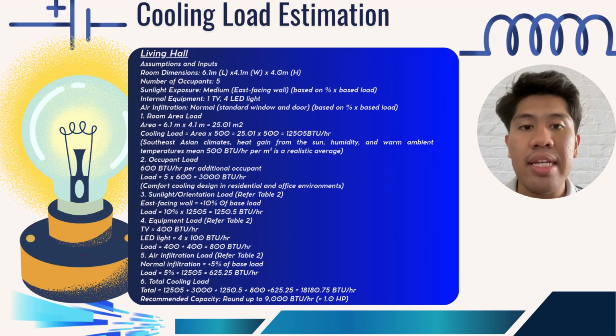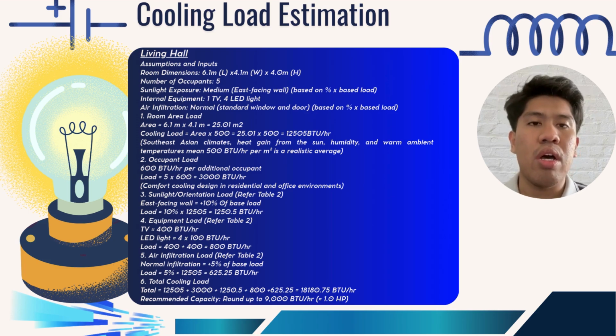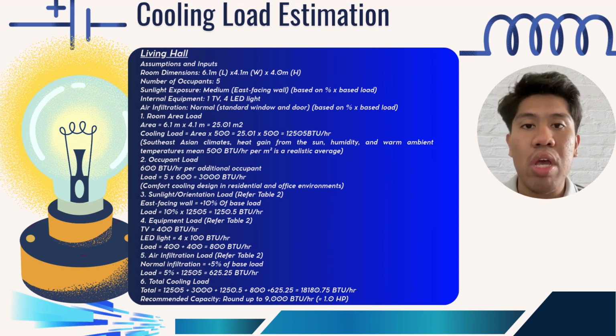The living hall has dimension of 6.1 meter in length and 4.1 meter in width, giving a total floor area of 25.01 square meter. In South Asia climate, a standard factor of 500 BTU/hour per square meter is used due to high temperature and humidity. So the room area load is 25.01 square meter multiply 500 BTU per hour, which gets 12,505 BTU per hour.